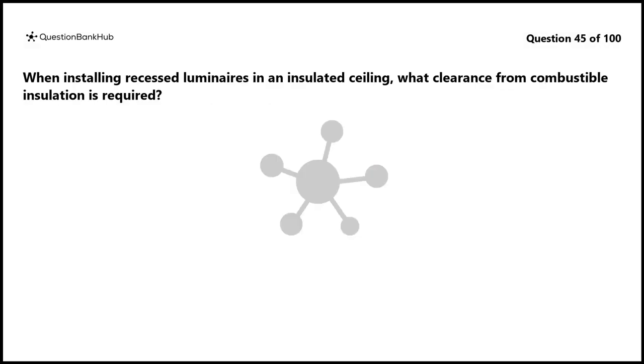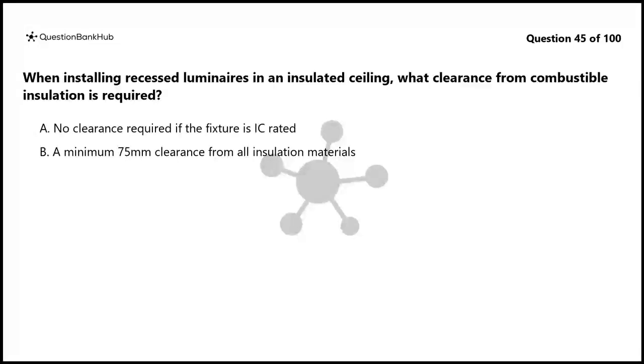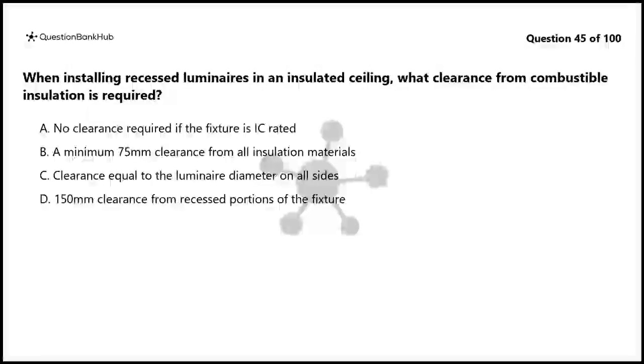Question 45. When installing recessed luminaires in an insulated ceiling, what clearance from combustible insulation is required? A. No clearance required if the fixture is IC rated. B. A minimum 75 mm clearance from all insulation materials. C. Clearance equal to the luminaire diameter on all sides. D. 150 mm clearance from recessed portions of the fixture.